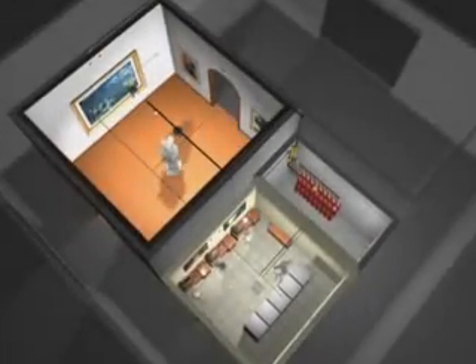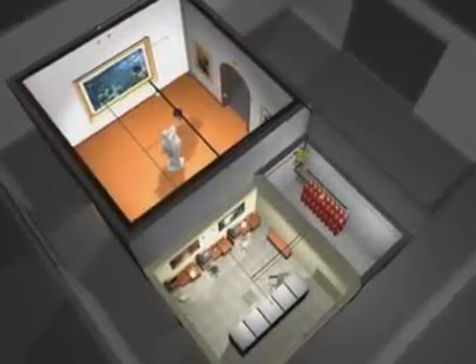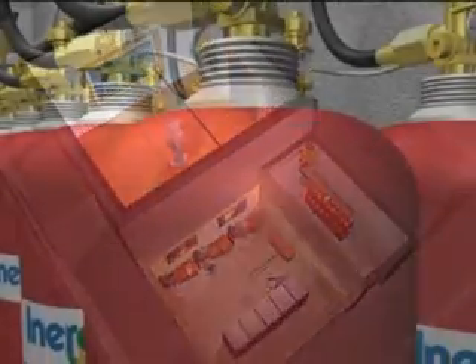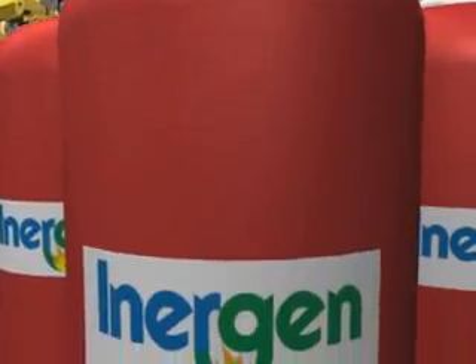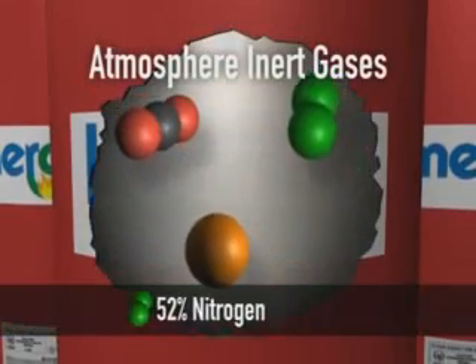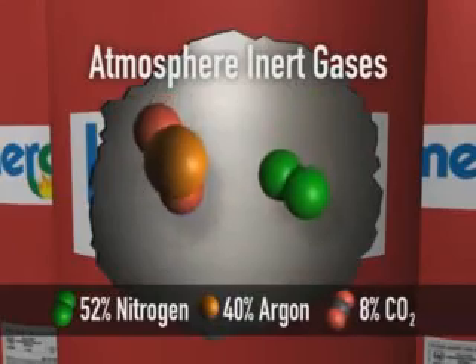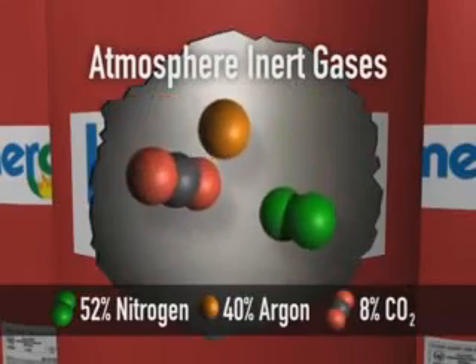An Inergen clean agent fire suppression system is both innovative and flexible in design. Inergen is a combination of three naturally occurring inert gases from the Earth's atmosphere. It is comprised of 52% nitrogen, 40% argon and 8% carbon dioxide, common components of the air we breathe.